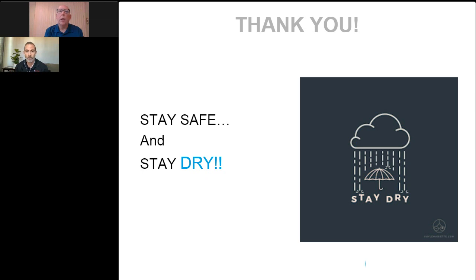Yeah, so again, we want to apply those basic concepts I spoke about. We've got to really pay attention to the lumen and how we're going to direct airflow through there. There are devices that you can use outside of a drying cabinet for flexible scopes. There's also scope cabinets themselves that can be used for flexible scopes. For drying robotic devices, we want to make sure, obviously, we follow the manufacturer's IFU, but if there's the ability to enhance that IFU to provide something that's thoroughly dry, a consistent, low, constant air pressure of warmed air through that device is what's going to render it what the study termed clinically dry.